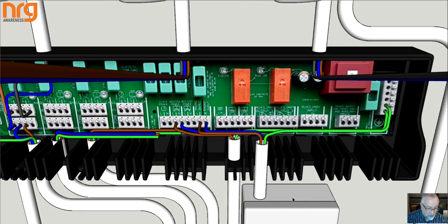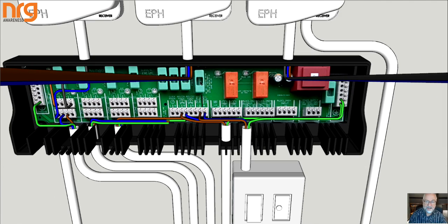So you come in from your double pole isolated switch. You've got your earth onto your earth block here. There's another earth block at the other side. And you have live and neutral going into your 5 amp mains fuse input. At that stage, you have a live track that travels right along the top of the board, fed from the 5 amp fuse. And so it's supplying power to the 4 1 amp fuses that control each of the 4 zones A, B, C, and D.